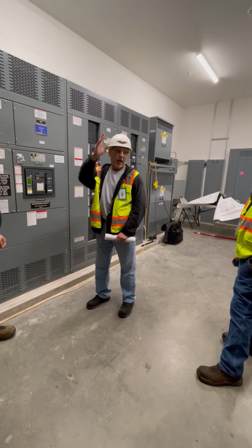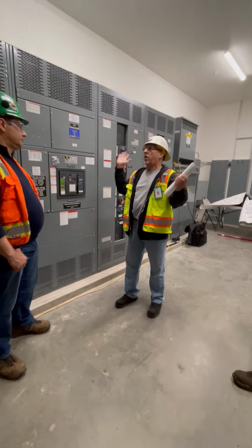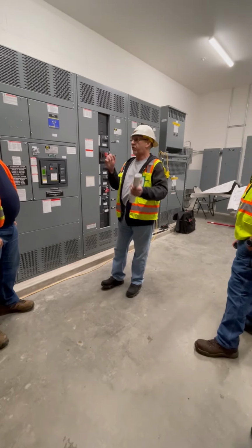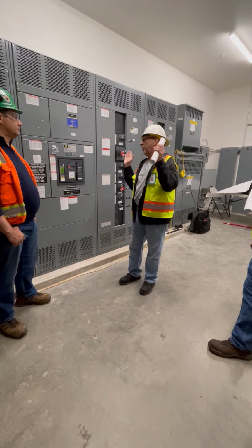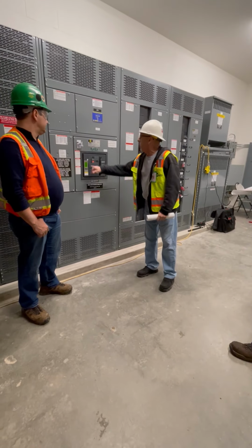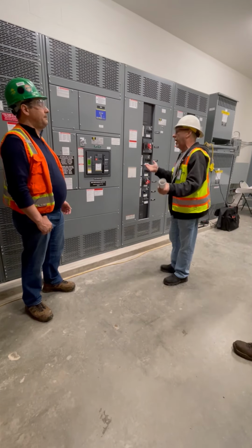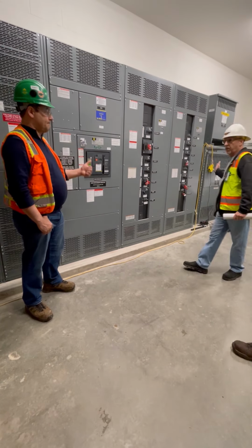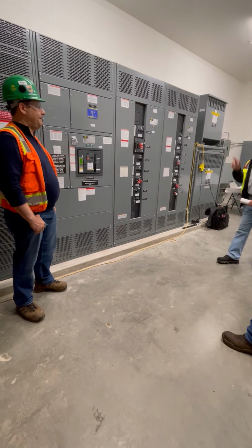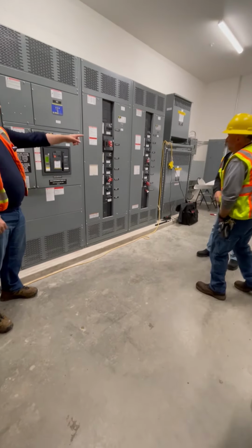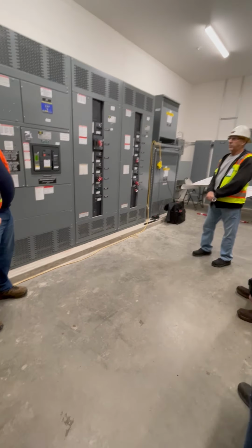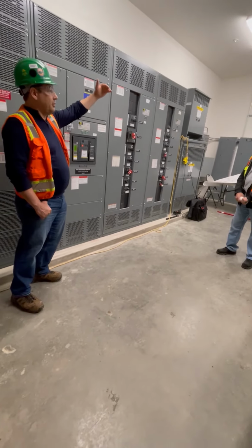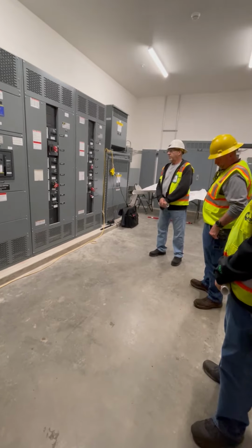Instead of guessing, when it happened at Fisher's Landing, we had no idea why the breaker was tripping, and troubleshooting was phenomenally a pain in the butt. There's no generator. You come here, it says ground fault, then you can say, okay, start doing it this way. Very handy to have that. And then you can use the one-lines for process of elimination to see what's on that feeder and then start going downstream to try to figure it out, right?